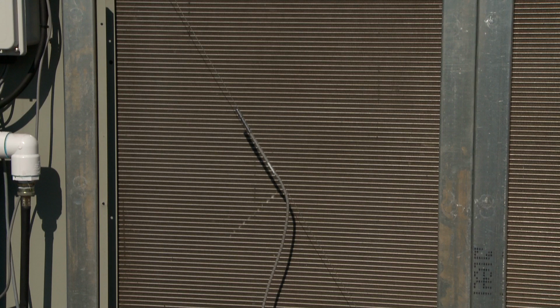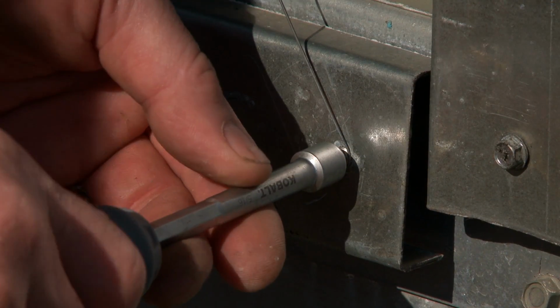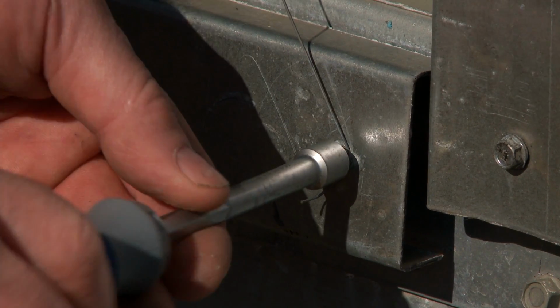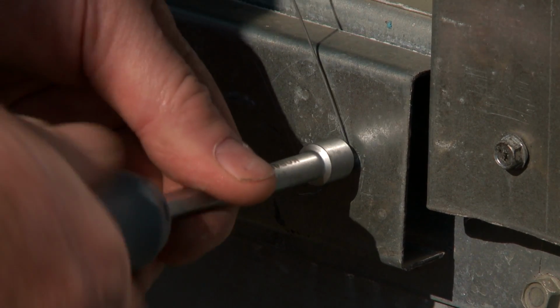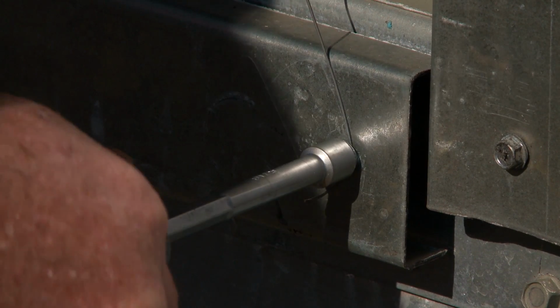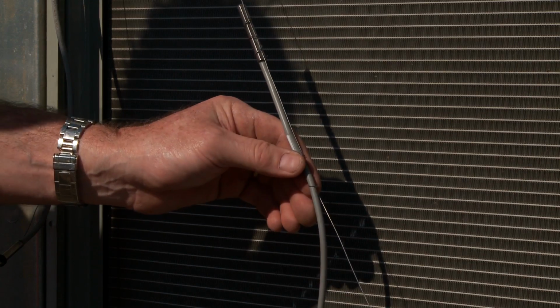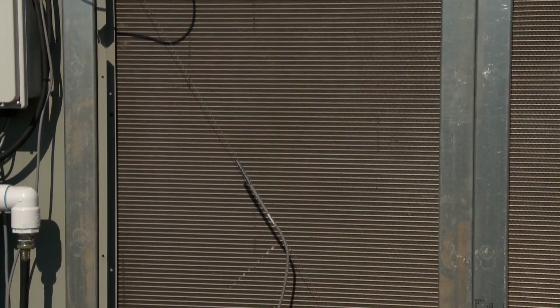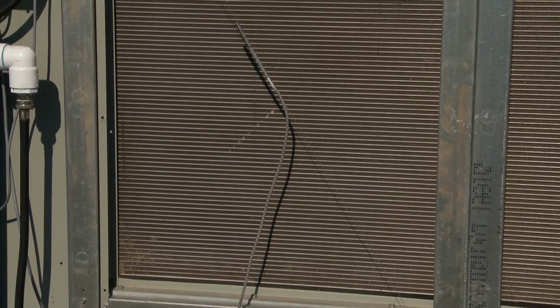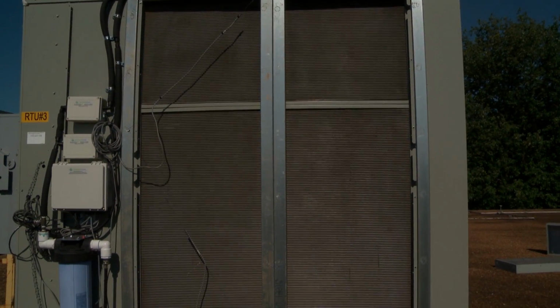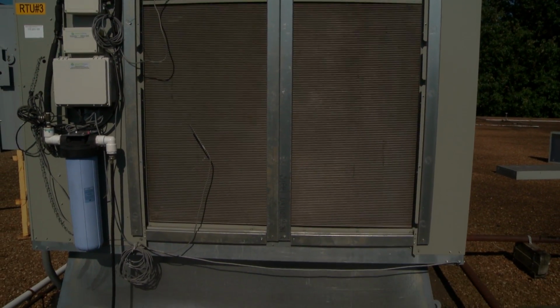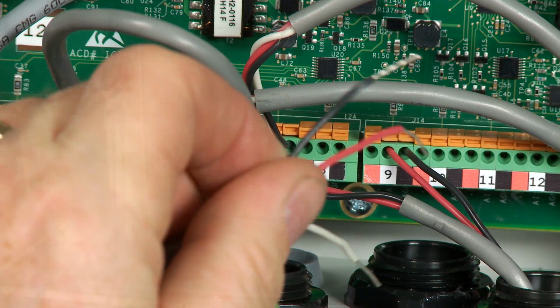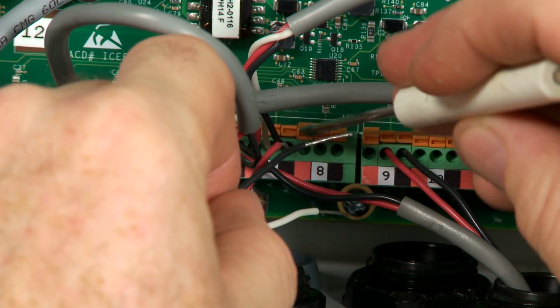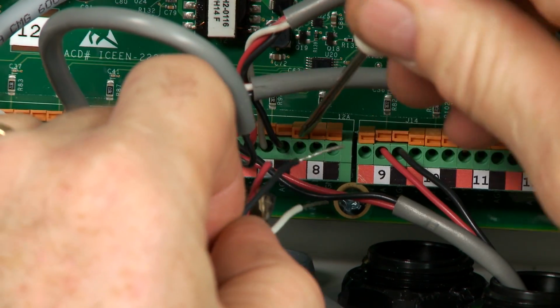Then, you must install the condenser air intake sensor. This sensor is mounted behind the Evaporcool evaporating medium. The valve box layout diagram will indicate the optimal location for this sensor. Care must be taken so that the sensor freely hangs in the air and doesn't come in contact with the condenser coil. Most often, the sensor is attached to a taut 22-gauge stainless steel wire. Connect the sensor leads through a cable grip on the controller box and attach to the board.